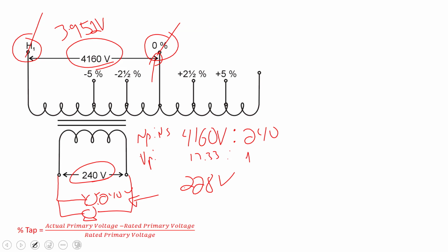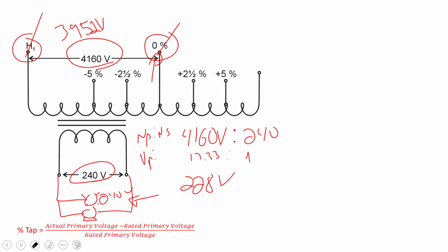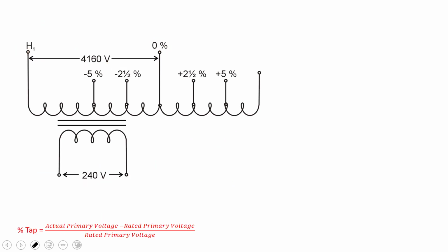Okay, so the light bulbs might be a bit dimmer. The motor's probably going to draw a bit more current. A lot of things that probably aren't good for the loads, and they may not last as long as they normally should. So this is a very common problem. So what they have is multi-tap transformers on the primary, and this is to compensate for variances in the primary voltage.